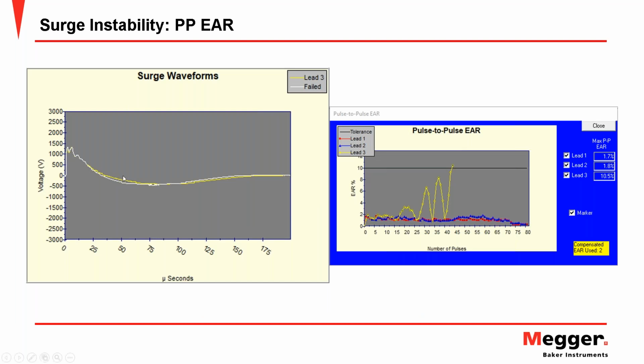And here we see an example of the shifting waveform, which is caused by, as the insulation arcs over internally, that causes an inductive change. The small inductance change causes the resonant frequency of this ring pattern to shift to the left. And that is represented in the P-P EAR graph as spikes or increases in the P-P EAR graph. And this is what we use for our protection, if you will.